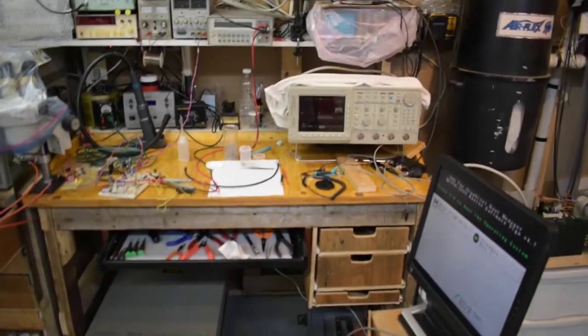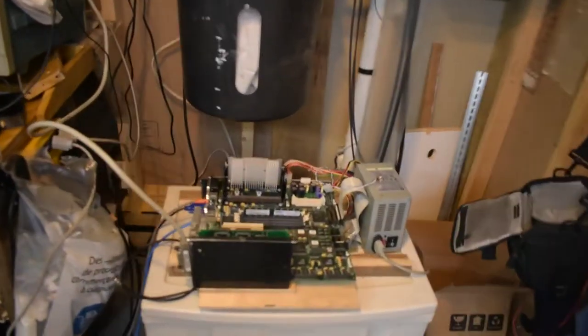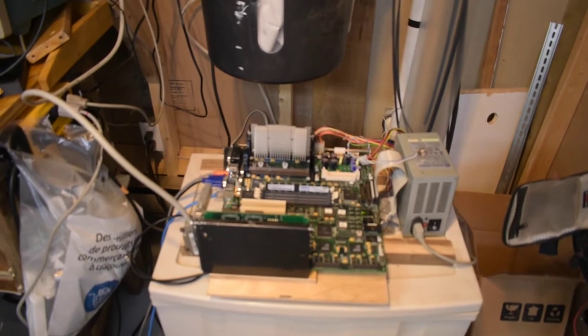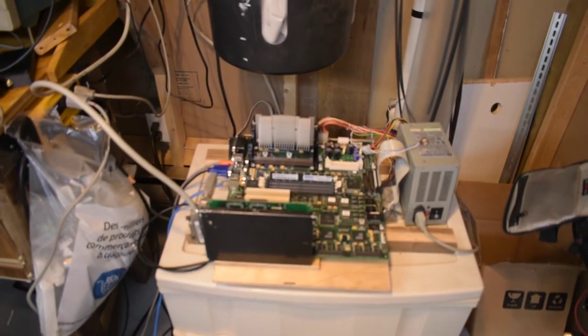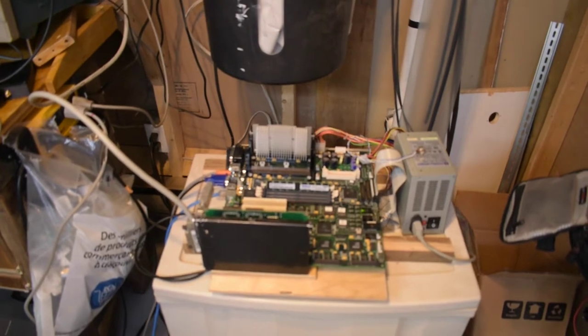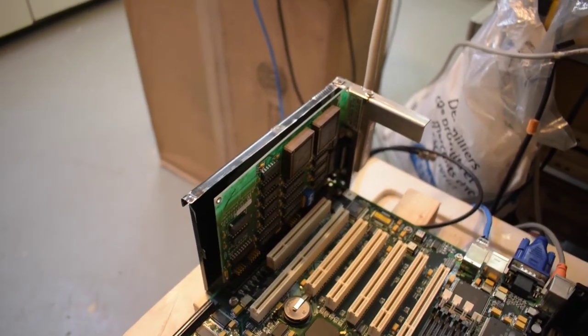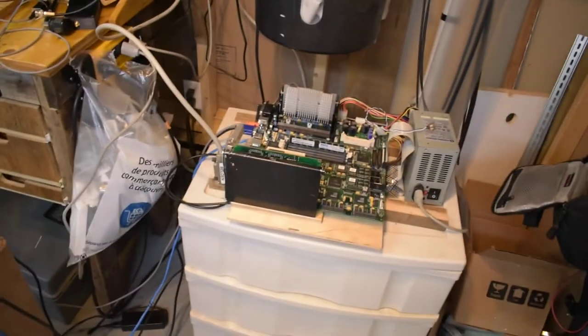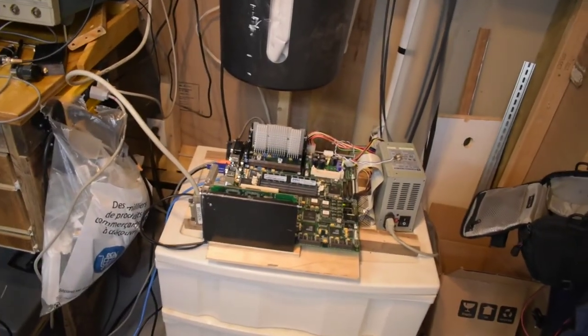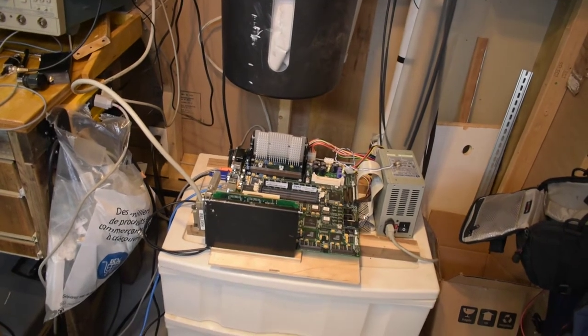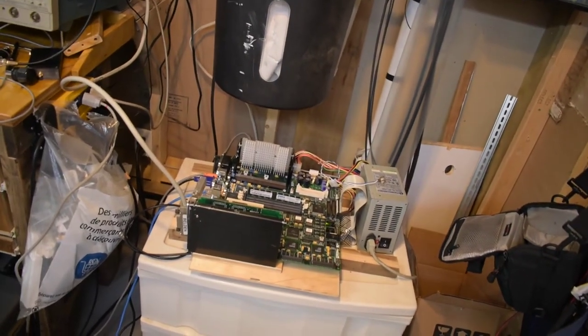The method I chose is to go with the old DOS computer. Of course, I threw out the last computer I had with ISA slots about 2 years before I got the scope. Anyway, so I had to buy a new one. And you need the ISA slot to get this GPIB interface card. And not just any of them, one of the models that are supported by the Tektronix field adjustment software. A bit more on that later, maybe.